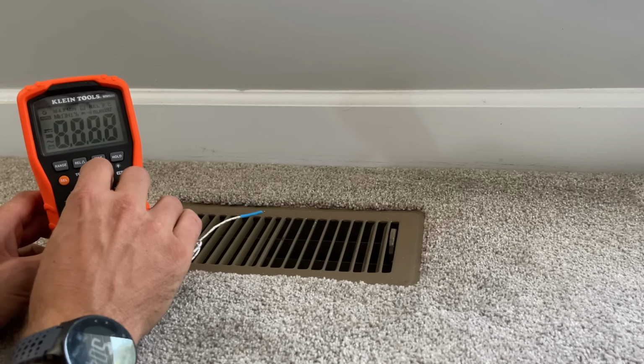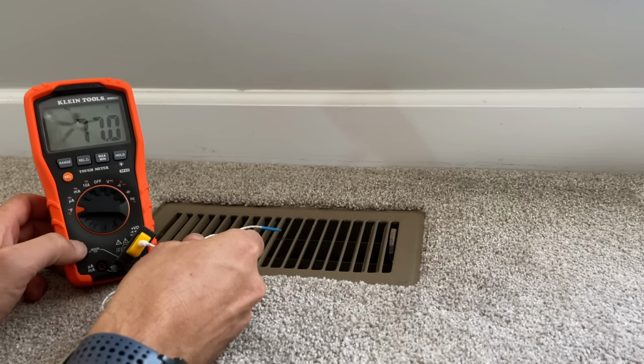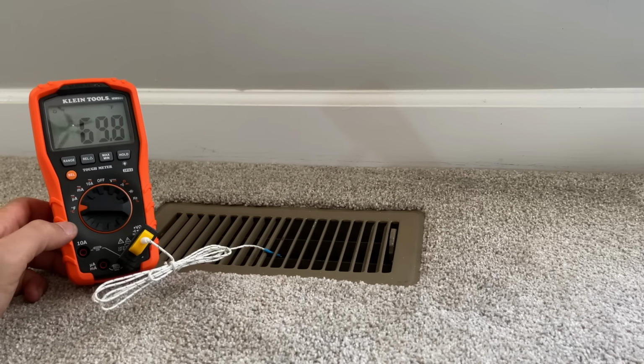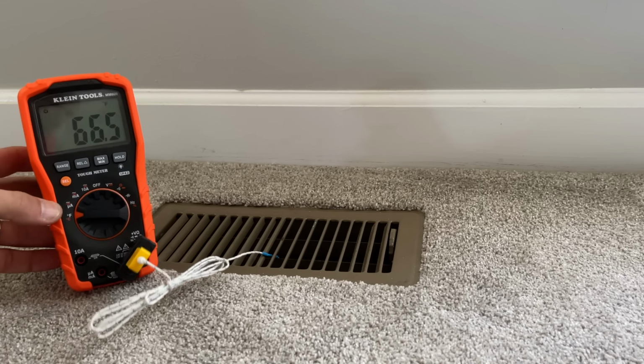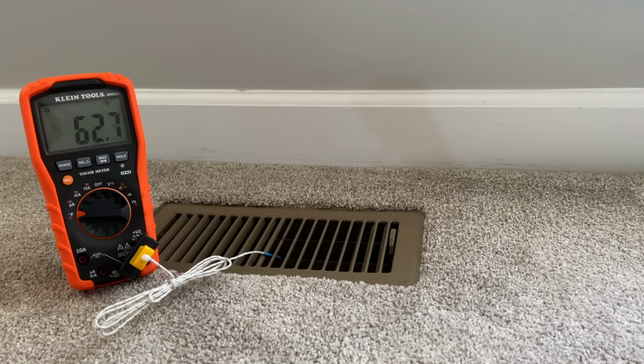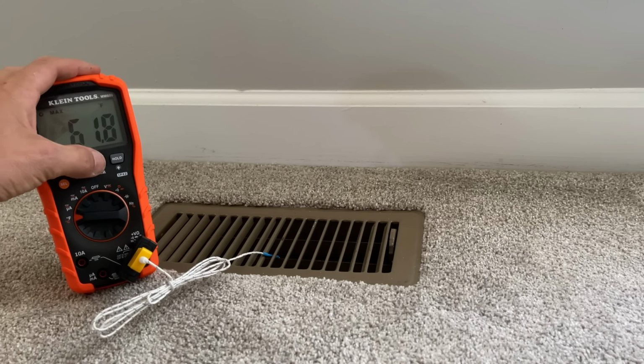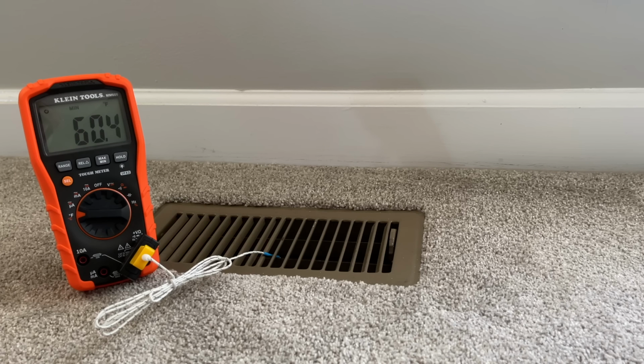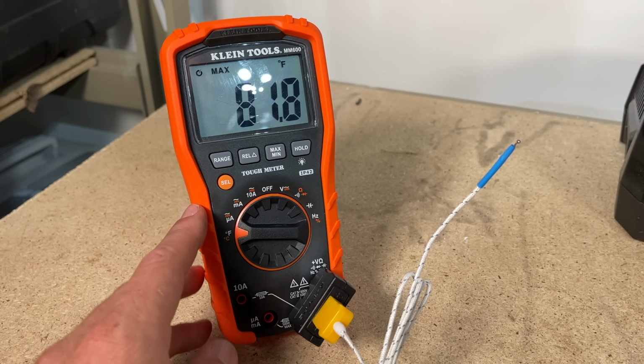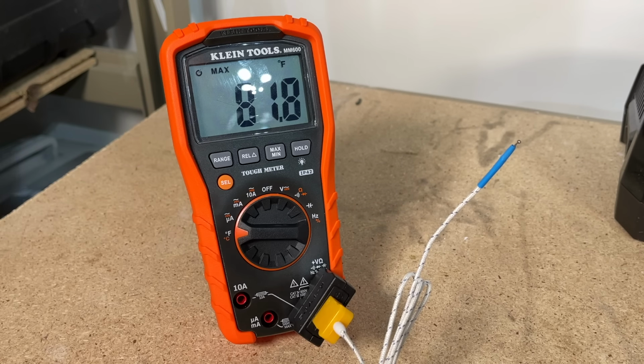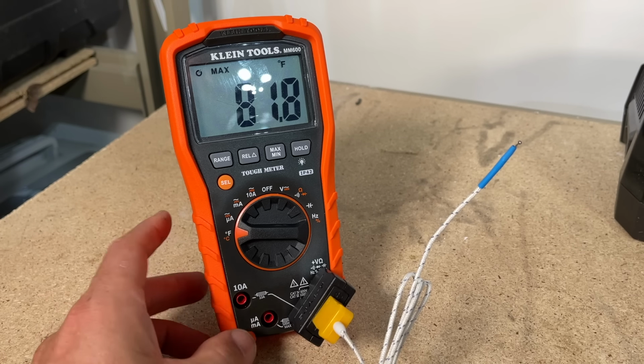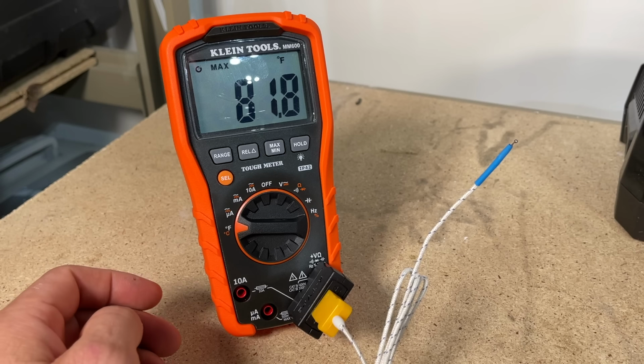The most common thing I use this for is HVAC—maybe checking how cold the air is coming out of a vent, or if there's an issue with the air conditioning. Or I'm trying to balance a system between the first and second floor. I'll take a measurement on the first floor, maybe do a max, let it run for about 15 minutes to reach steady state, then go to the second floor and do the same for 15 minutes. That gives me the different temperatures to help balance the system. That's really it on temperature—very handy and easy to use.